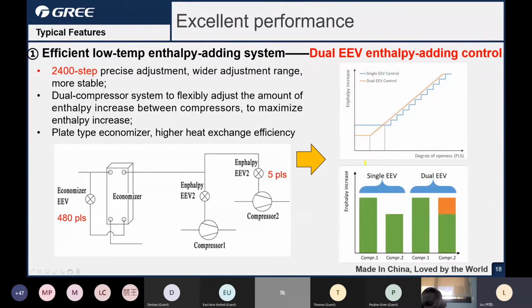Now, what is the advantage of these two expansion valves? If there is just a single expansion valve, every time in the opening adjustment, each stage may be 10 pulses or 20 pulses. You can see the height of each stage is very high, because the precision with just one expansion valve is not really precise. However, if there are two dual expansion valves, you can see the adjustment of the valve is smoother. That means the control will be more precise for the unit output. Okay.